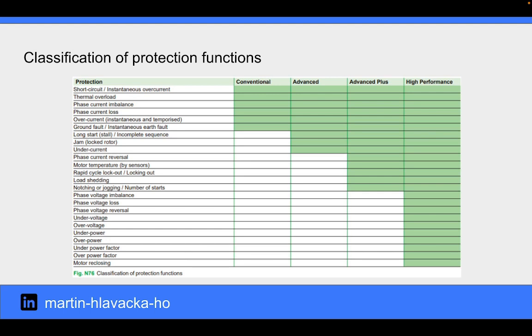Conventional protection functions apply to every type of motor application. Advanced protection functions apply to more sophisticated machines requesting special attention. Advanced plus and high performance protection functions are justified for high power motors, high demanding applications, or motors in critical processes, or whenever ground current must be measured with high accuracy. In addition, high performance protection functions are not based only on current like the Advanced Plus scheme, but also on voltage.